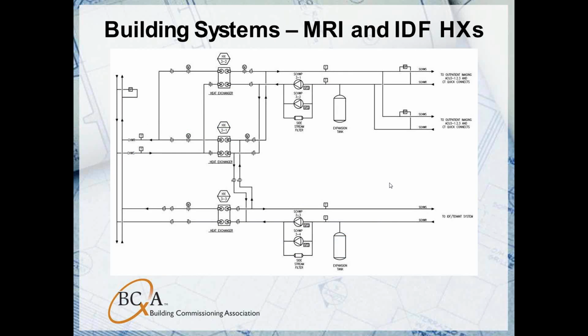These are the heat exchangers located on the 3rd floor of the building. These provide both a pressure break and a separation between the chilled water side and the process water loops. Two heat exchangers, heat exchanger 3.2 at the top and heat exchanger 3.3, operate in duty, and the middle heat exchanger, 3.1, operates as a standby, and the way it's piped, it can serve either the data loop on the bottom or the MRI CT loop on the top. The process loop pumps here and here are controlled to a loop differential pressure set point, and motorized valves on the chilled water side of the heat exchangers modulate to maintain a process loop supply temperature here and here.